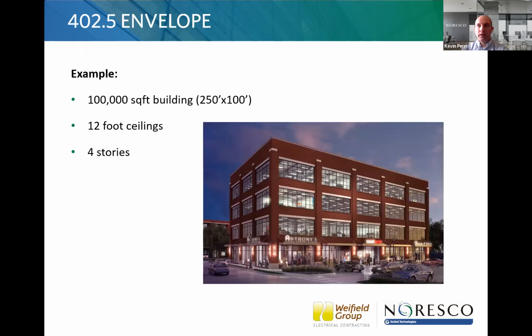So you might ask, how can I calculate that? Well, here's an example building. For the sake of time, I'll let you do this on your own. However, if you want to do the math, it comes out to be about 83,600 square feet of envelope area. And remember, Denver allows you 0.4 CFM times that value, and that would be your allowable leakage for that building. So it's an easy calculation to do. You can do it in design to see which components you need to focus on being tight, and connections need to be tight, and be prepared for your testing.